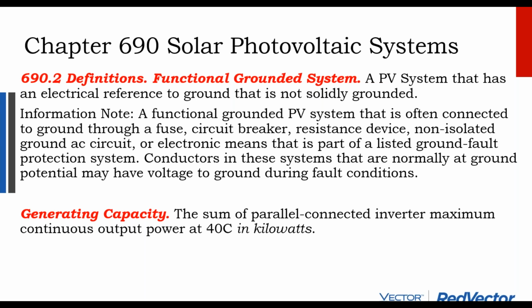Well, normally your inverters have ground fault detection, but then you had this negative blind spot in the ground fault detection of these negatively grounded inverters. And so the solution was, well, we're going to stop doing ground fault detection with negatively grounded inverters. We're going to have what's called a floating inverter. And the difference between a floating inverter and a negatively grounded inverter is you no longer have that negative to ground direct connection. Instead of just fusing the positive sides and having the negative side tied off to ground, you now have fuses on both the positive side and the negative side with no direct connection to ground.